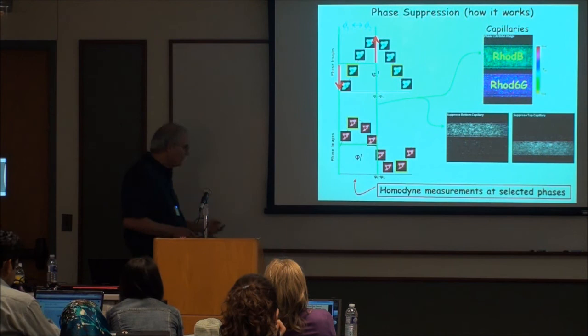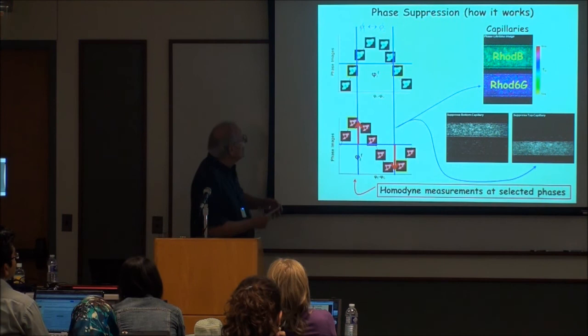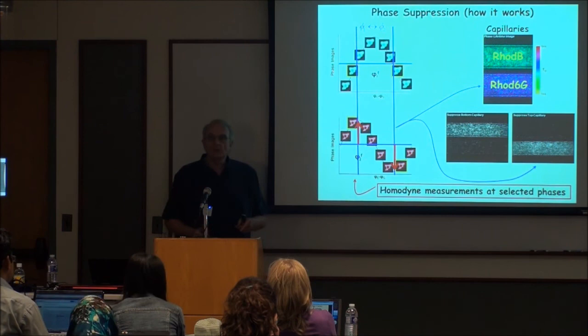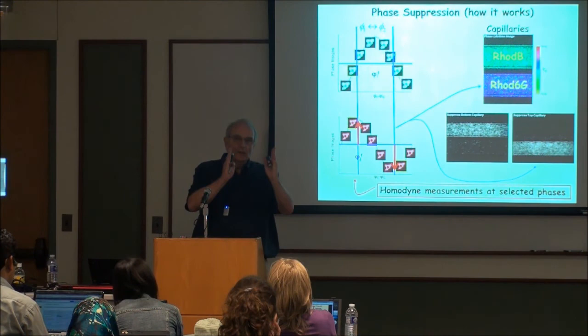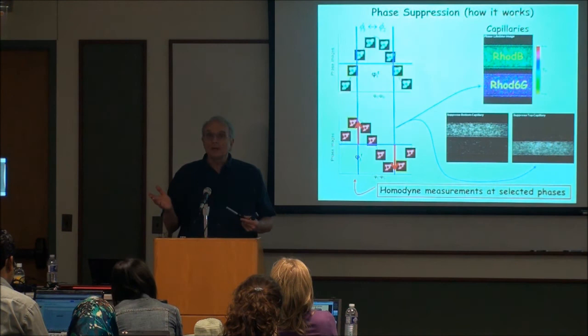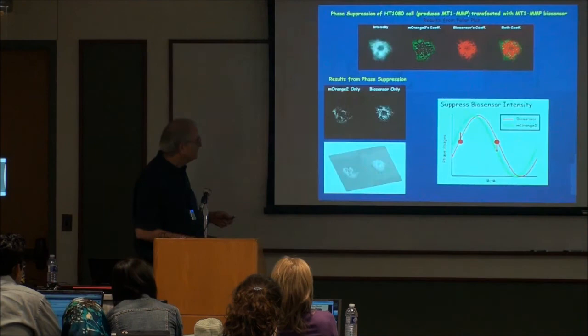If we set up our instrument to gather just two specific phases, one component disappears and we can see only the other one. We can either see this one or that one — and that's an immediate measurement: just two images. We can select those two phases wherever we want, so we can look for specific things. We can say, 'I don't want to see something that has a certain lifetime' — which is very convenient because quite often the background has a lifetime we don't want to see. We just set it up so we don't see that, and only the other component remains.